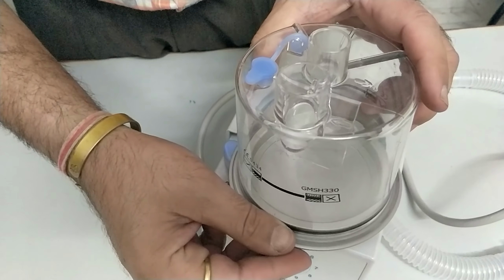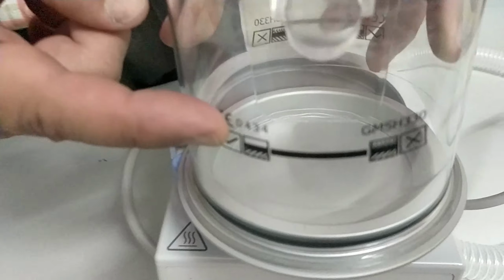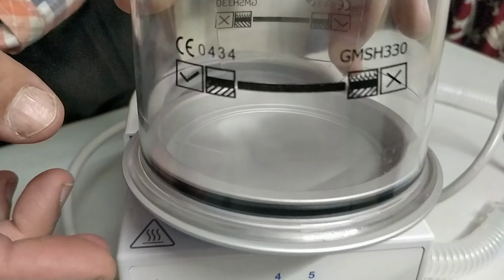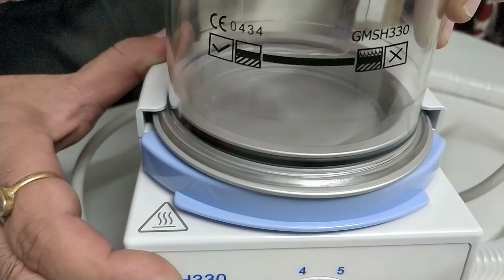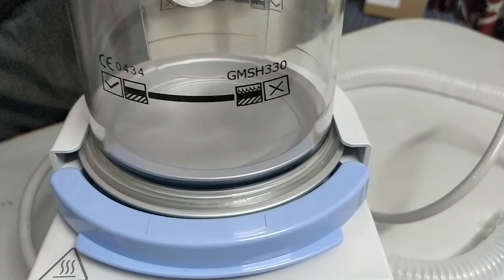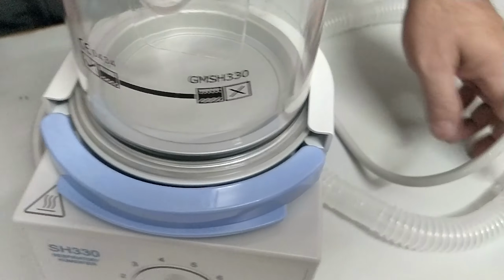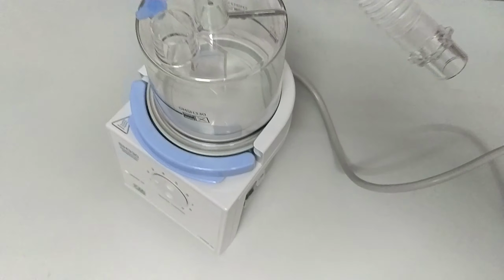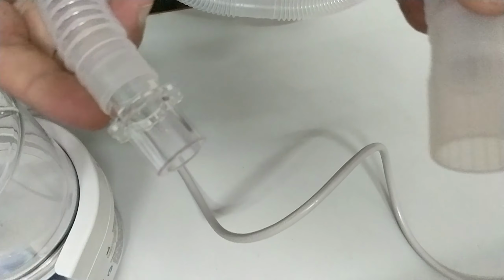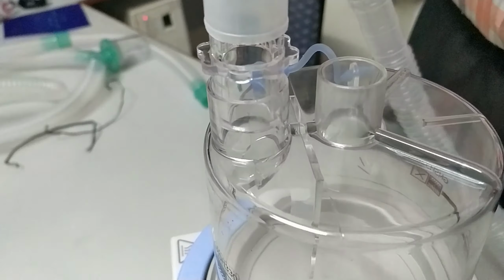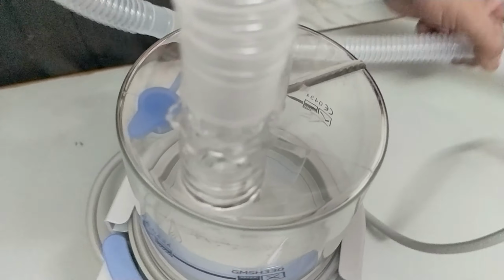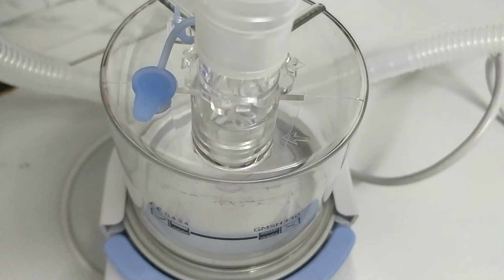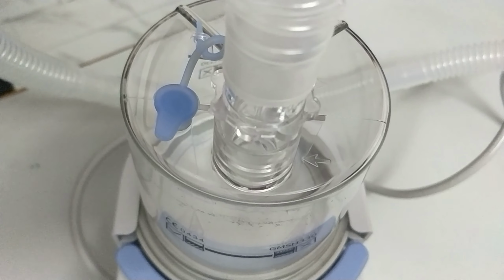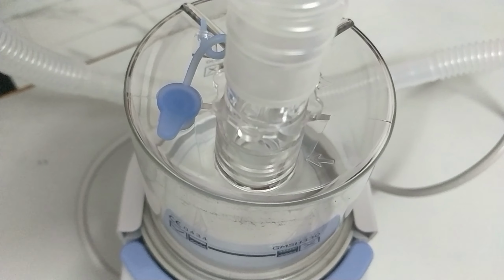Now we have to put water up to this level. This is the water level indication. You insert the chamber, slide it inside and it gets locked. Now the humidifier is not yet working. Now we have to connect the circuit which the machine has given. There are two ends of the small limb which is normally provided. One end will go to the ventilator and the other end will go to the inlet of the chamber. So this is the inlet of the chamber. It gets connected to the inlet, and now we have to connect further the circuit provided with the ventilator machine.